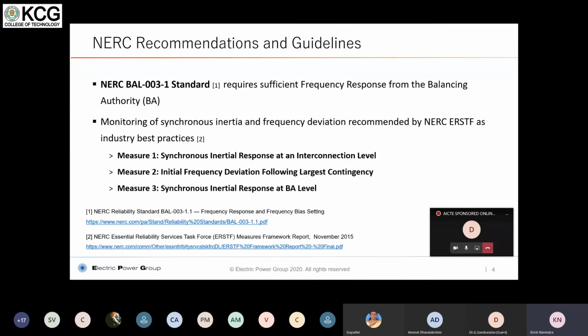In India, the one good thing is, because the grid is highly synchronous at this point, the north, south, east, west, everything is joined as one grid, there is a huge support of rotational mass available in the system that is still helping the grid not to take the frequencies to a very worst level at this point. But in the future, because of the continuous growth of solar and other penetrations within India, you will have a bigger problem with inertial support of the grid.